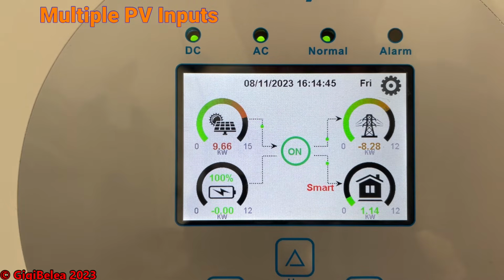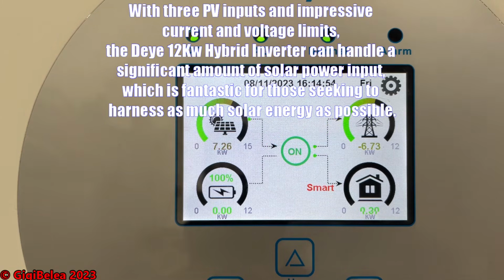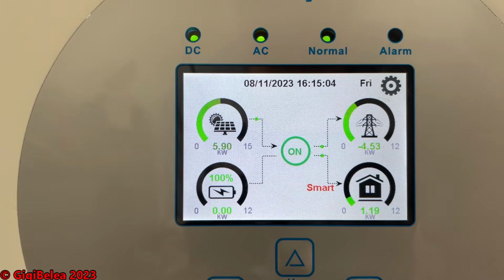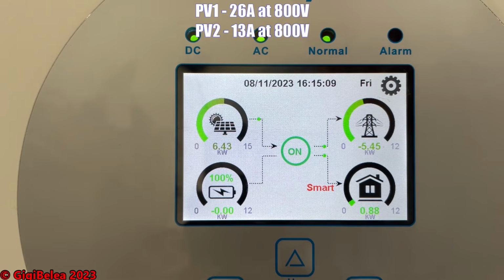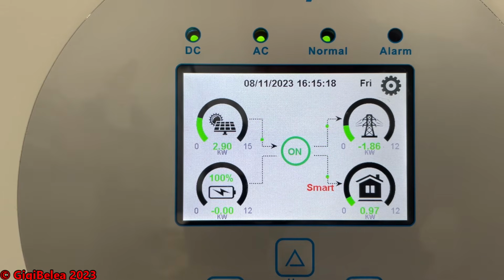Another important factor for me when I purchased this inverter was the number of strings that I can connect to the inverter, and this one has 3 PV input ports. On the PV1 you can go up to 26 amps in current and 800 volts. On the PV2 you can go up to 13 amps and 800 volts. So PV1 supports 2 strings in parallel, and PV2 supports 1 string, and I have 2 strings on the south and 1 string on the west.